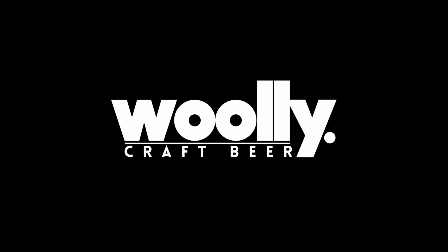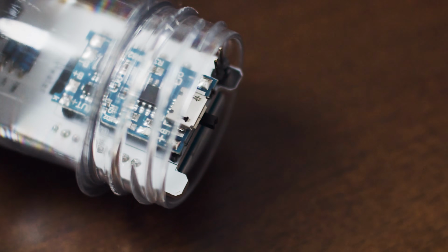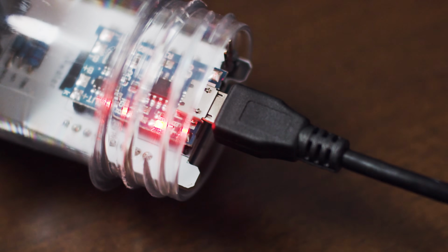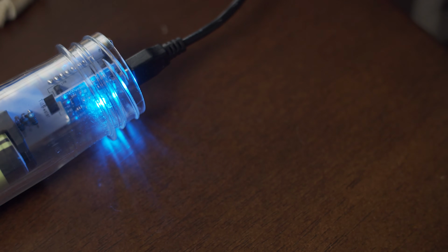The iSpindel results are only going to be as good as your calibration, so this is a really important step to get right. And the first thing to do is to make sure that we've got the iSpindel fully charged. To charge the iSpindel, we're just going to take off the lid and connect a micro USB cable into the top USB port of the iSpindel. The light will be solid red on the iSpindel while it's charging, and it will change to solid blue as soon as it's finished charging, which might take a few hours.